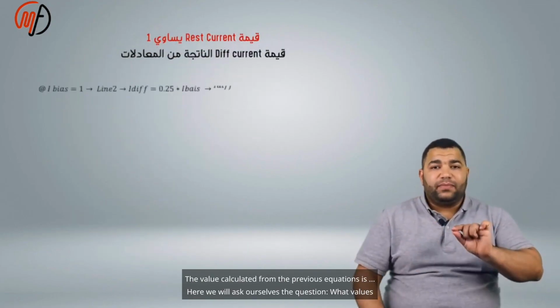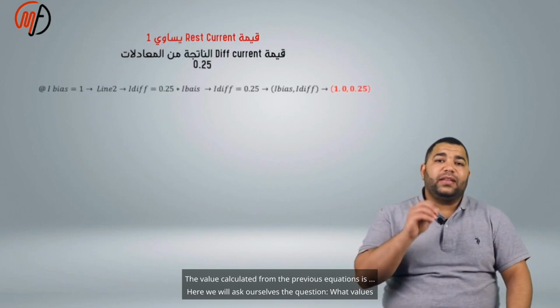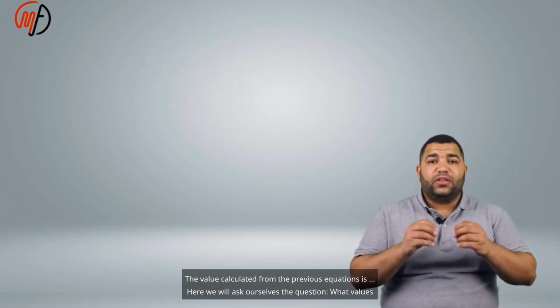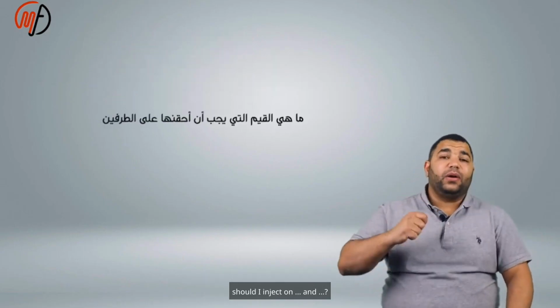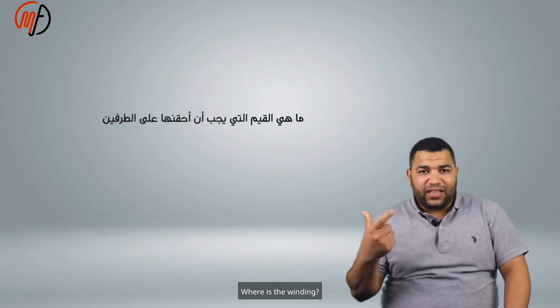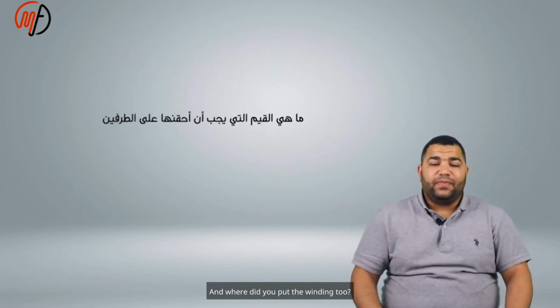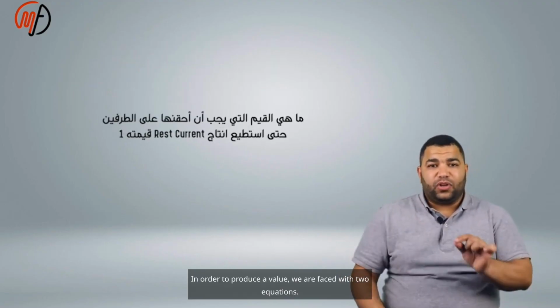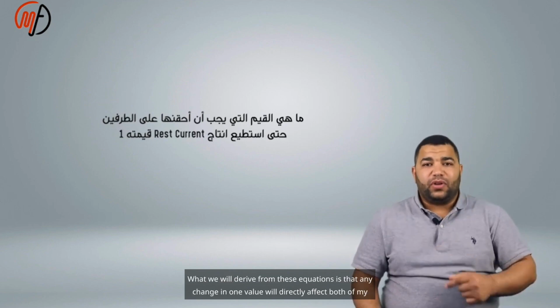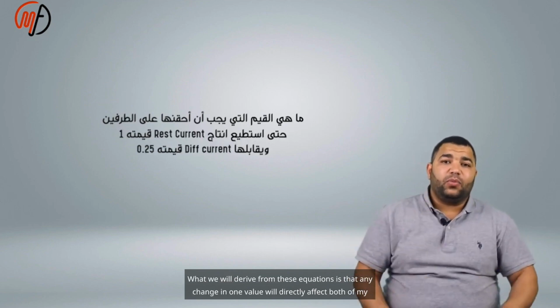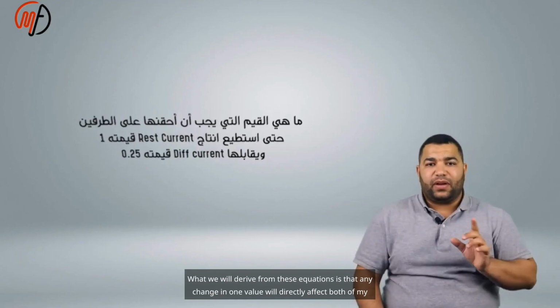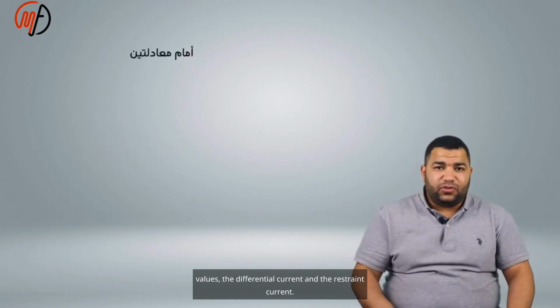The value calculated from the previous equations is, here we will ask ourselves the question, what values should I inject, and where is the winding? In order to produce a value, we are faced with two equations. What we will derive from these equations is that any change in one value will directly affect both of my values, the differential current and the restraint current.